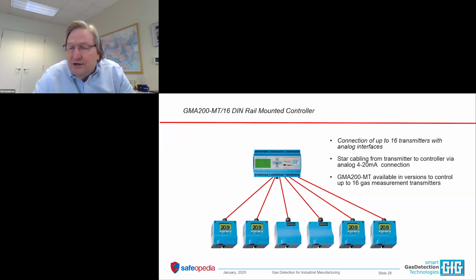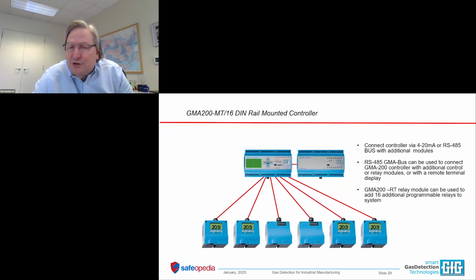The whole idea of a 4 to 20 milliamp analog connection is an industry standard approach that is used not only for gas detection equipment, but all kinds of other equipment that might be present and used for measurements on site. Besides the analog 4 to 20 milliamp connections that you have with the controller, it can also talk to other controllers or modules or equipment by means of a digital signal.